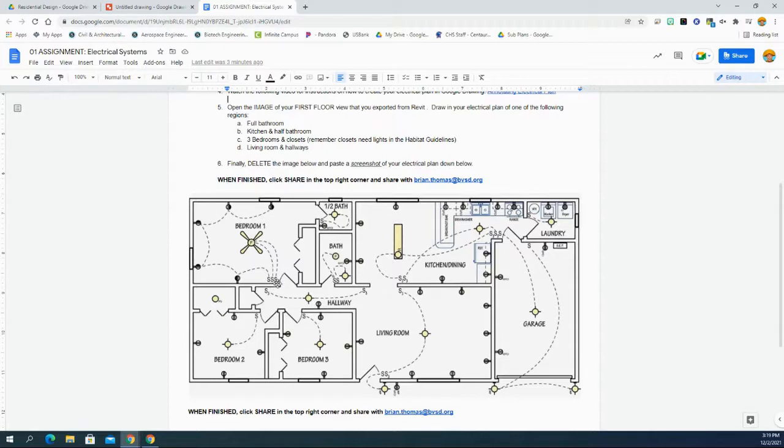This switch, SF, goes to switch for the fan. This switch goes to the light. So that's where those are different, S and SF. And then in the bathroom, you have a switch for the fan. We don't put SF because there's a line going directly to that. So you don't need to differentiate that one. And then finally, you have all of your electrical receptacles. By code, these need to be certain distances apart. Usually they're about 6 feet apart, so that they're frequently spaced. I'm not going to have you go that detailed into it.